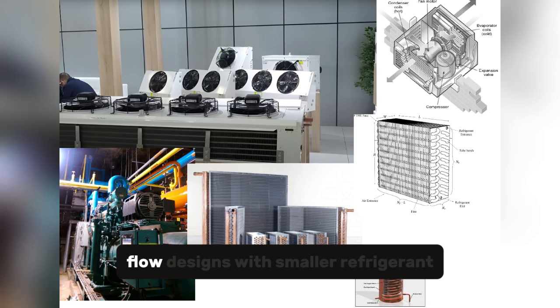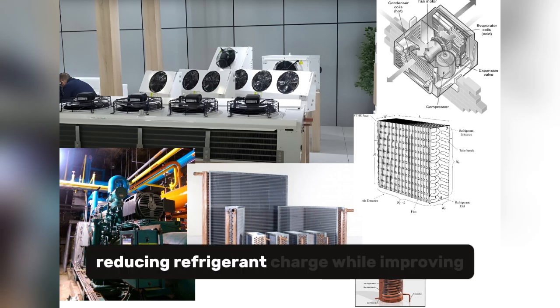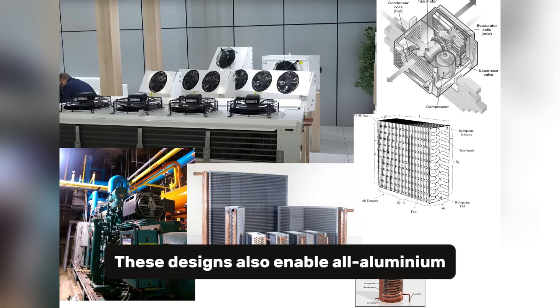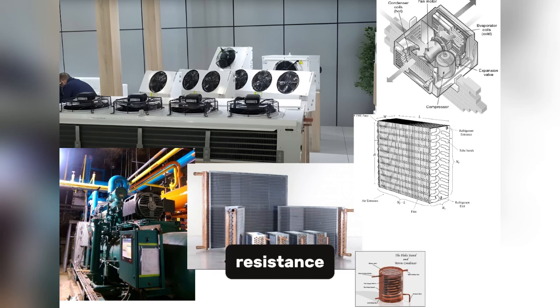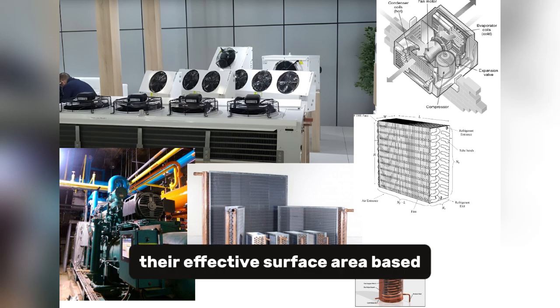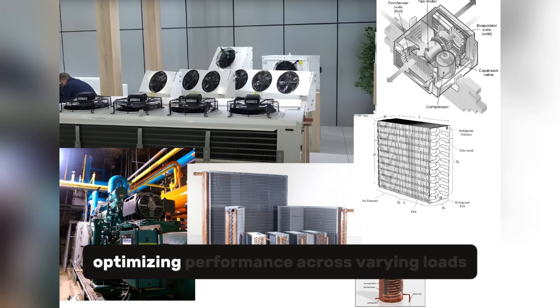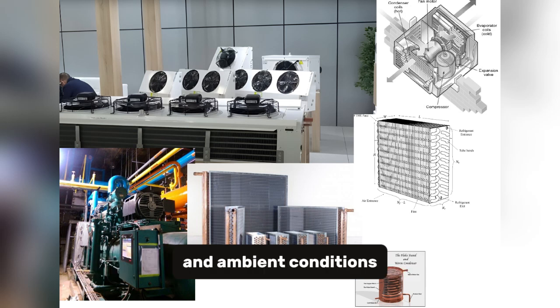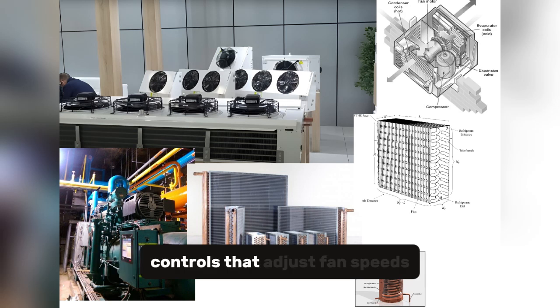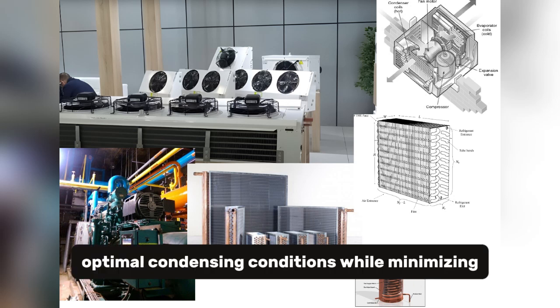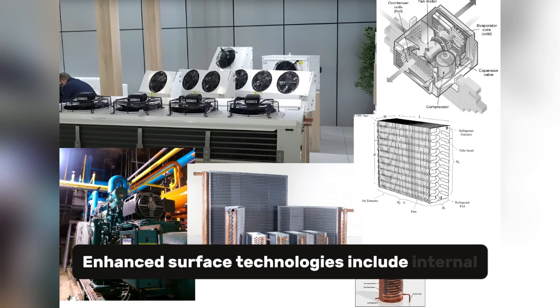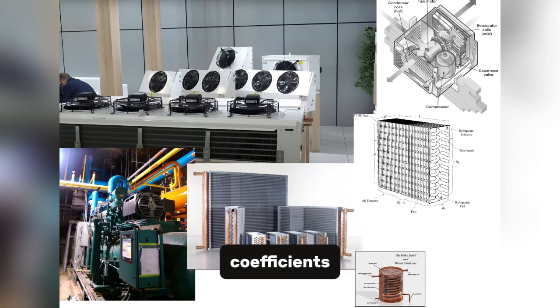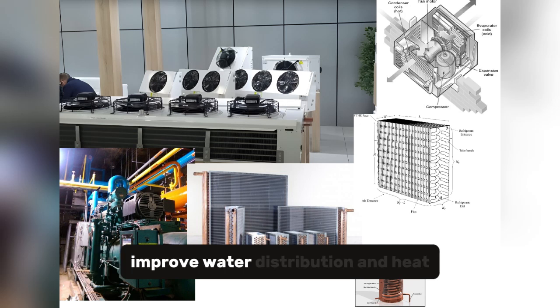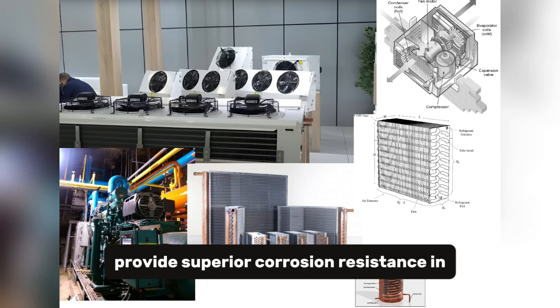Microchannel heat exchangers use parallel flow designs with smaller refrigerant passages, reducing refrigerant charge while improving heat transfer. These designs also enable aluminum construction, reducing weight and improving corrosion resistance. Variable geometry condensers can adjust their effective surface area based on operating conditions, optimizing performance across varying loads and ambient conditions. Smart condensers incorporate sensors and controls that adjust fan speeds, water flow rates, or damper positions to maintain optimal condensing conditions while minimizing energy consumption. Enhanced surface technologies include internal and external fin enhancements that increase heat transfer coefficients. Hydrophilic coatings on evaporative condensers improve water distribution and heat transfer. Advanced materials like titanium tubes provide superior corrosion resistance in harsh environments.